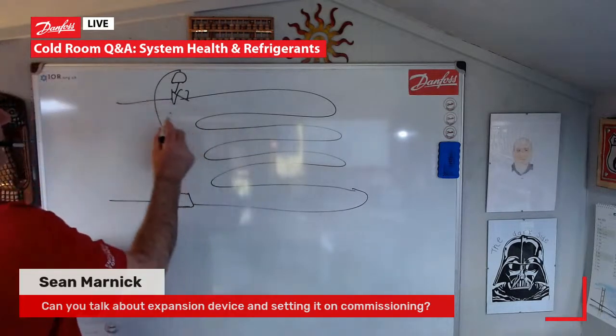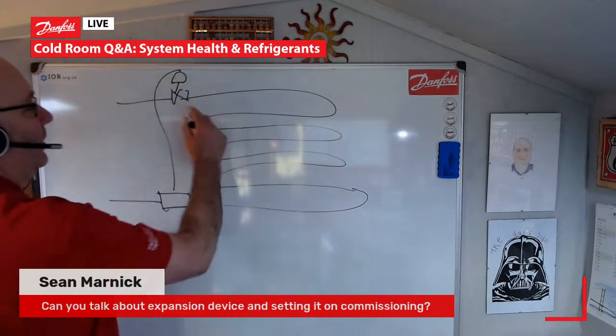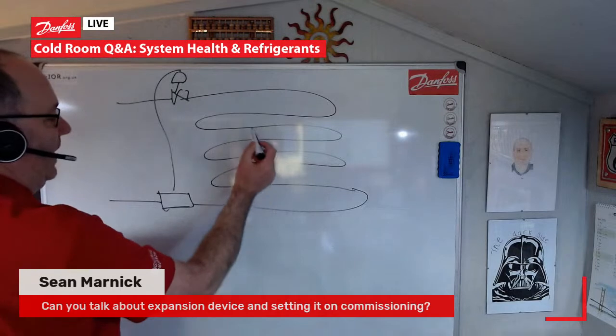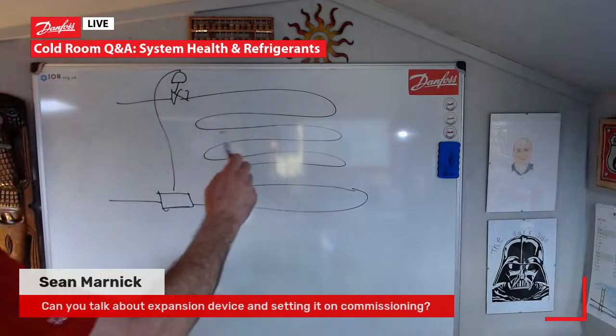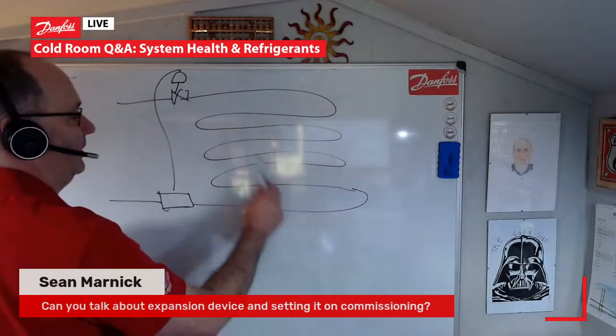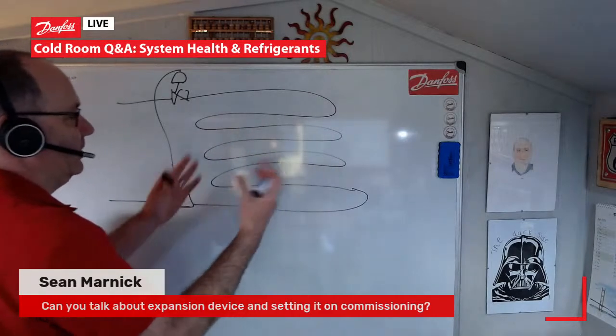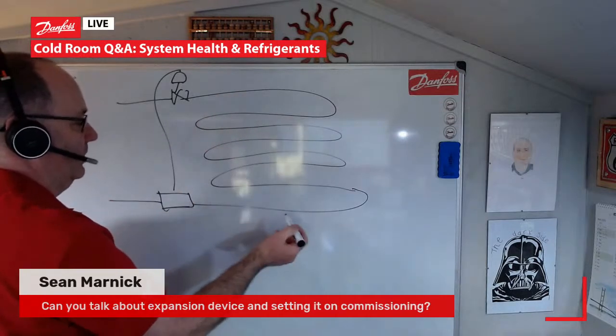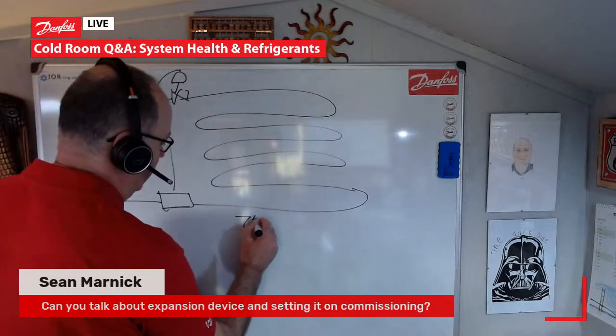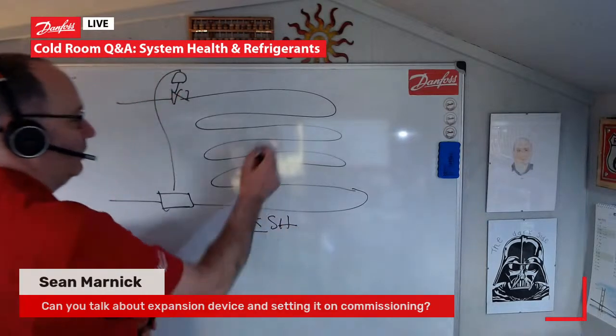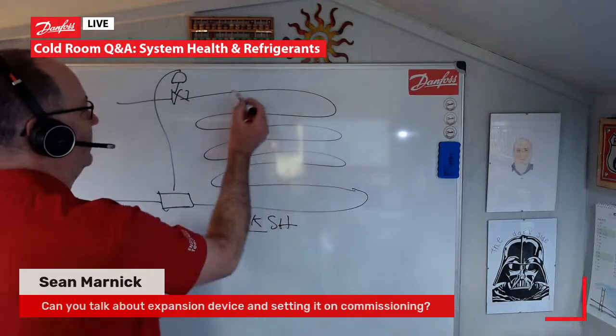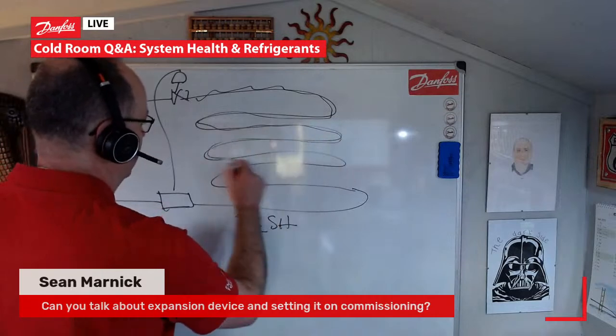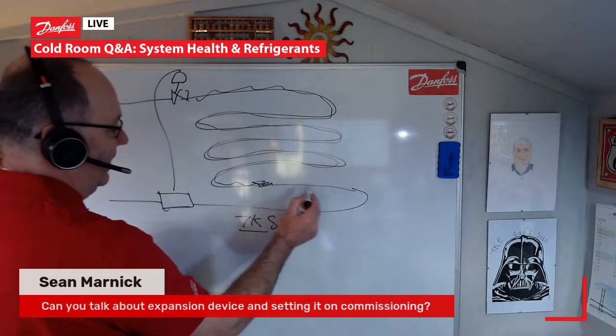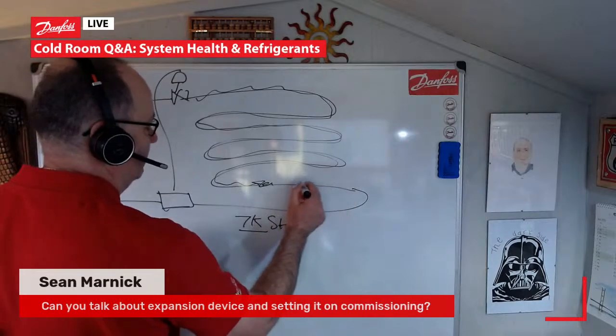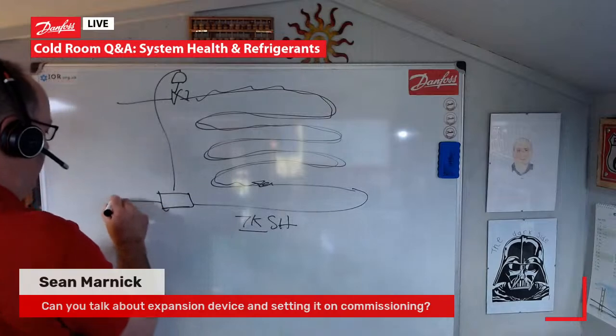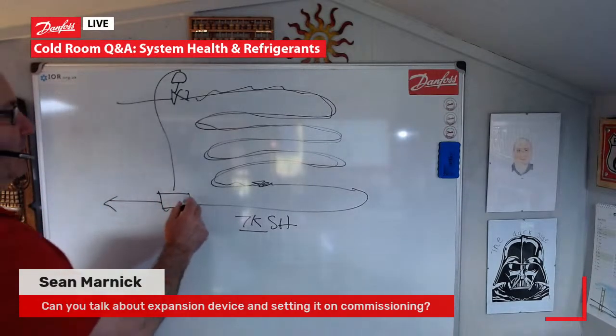Now, the basic idea is that we have our expansion device and we expand that liquid into our evaporator. And we want to have, let's say, a refrigerant liquid vapor mix in that evaporator as much as we can. So we want to utilize the whole surface area of that evaporator to get our duty. Now, if we have, let's say, a 7K superheat, we would be utilizing the majority of that evaporator. So we'll have liquid boiling off all the way down the evaporator to maybe somewhere there. And then we've got that part of the evaporator for the superheated refrigerant. And we've got vapor coming back down the suction line to our compressor, which is most important.